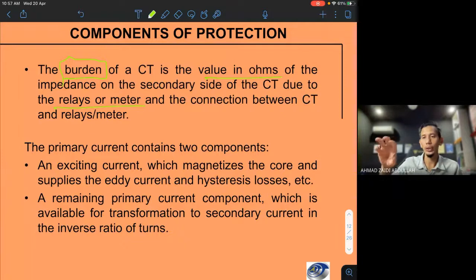And then you check, is it possible to apply or not? Okay, but because in the market we have a lot of CT, you need to select one suitable for your design. You cannot simply pick any size of CT. You need to know which is very suitable for your project, and it normally depends on the burden value.